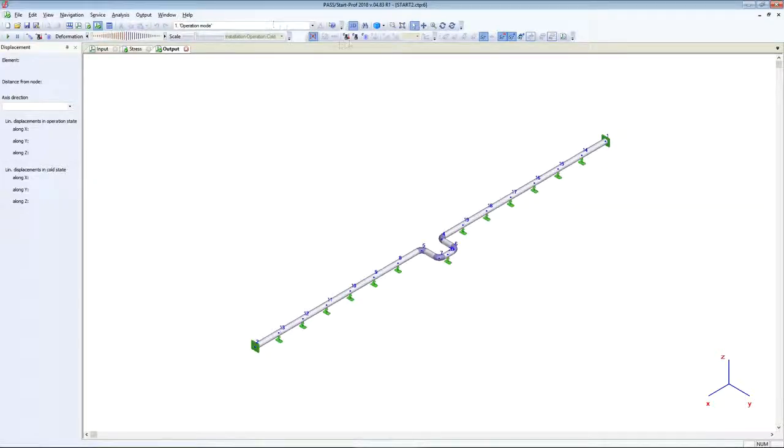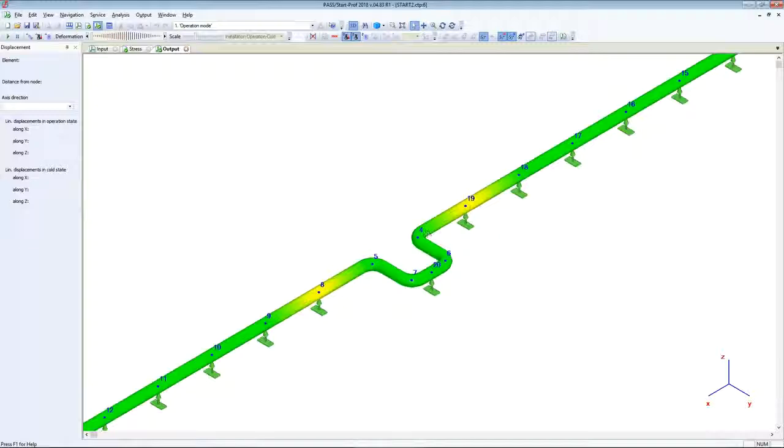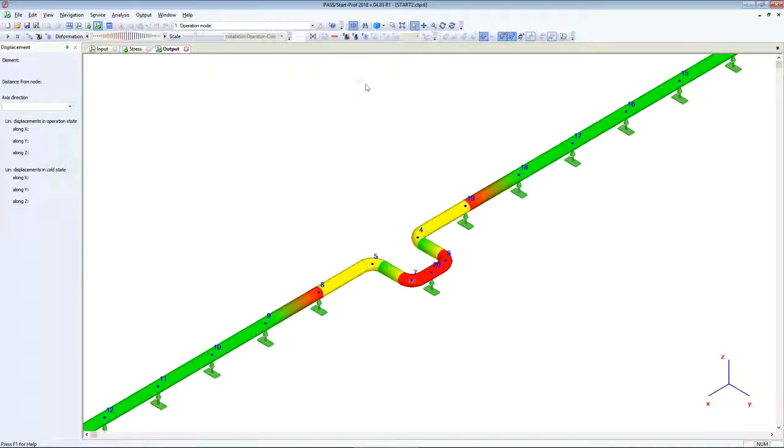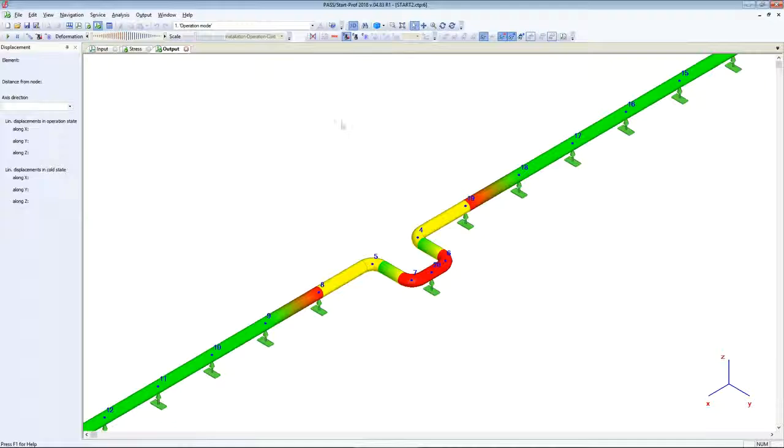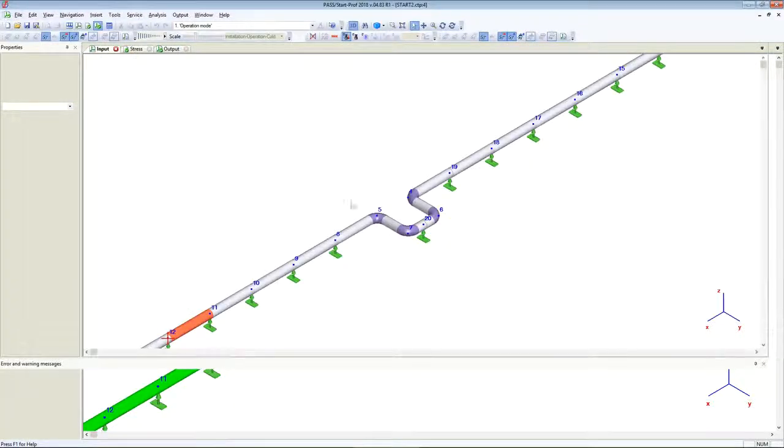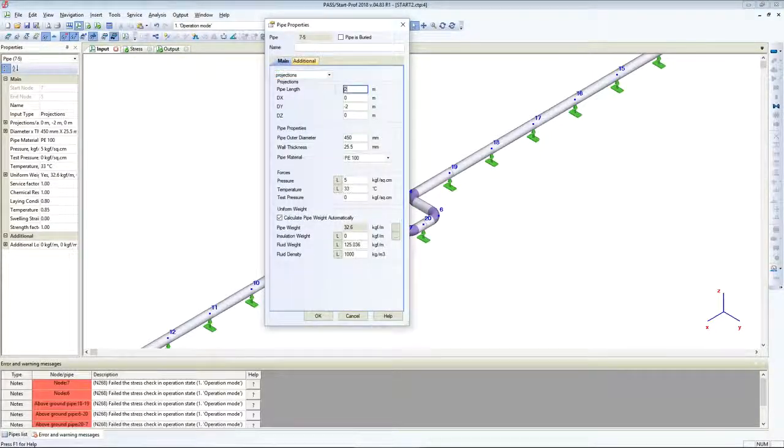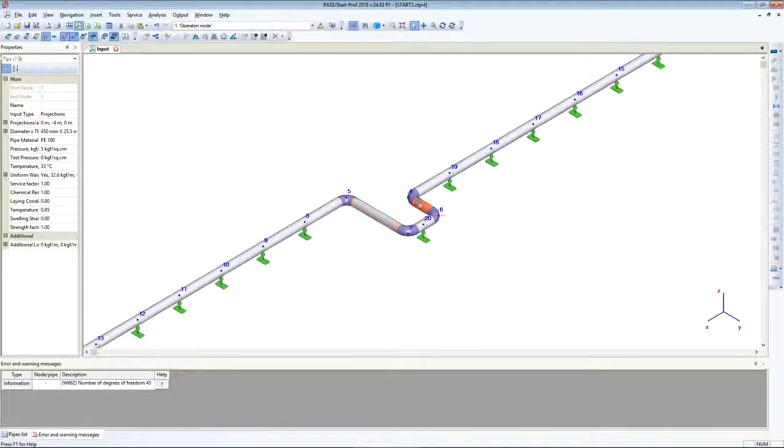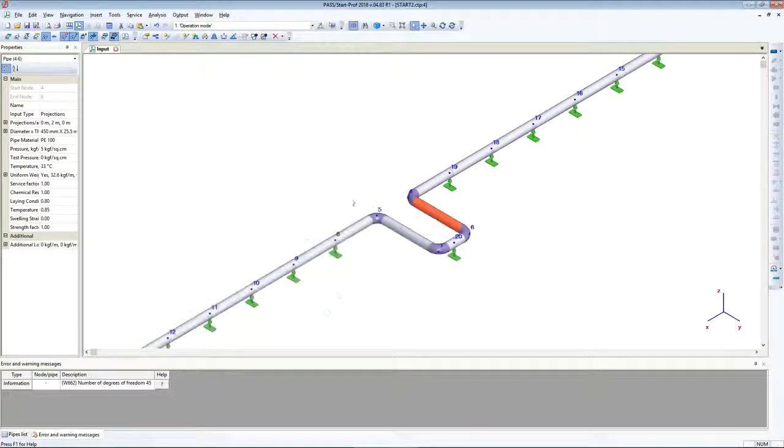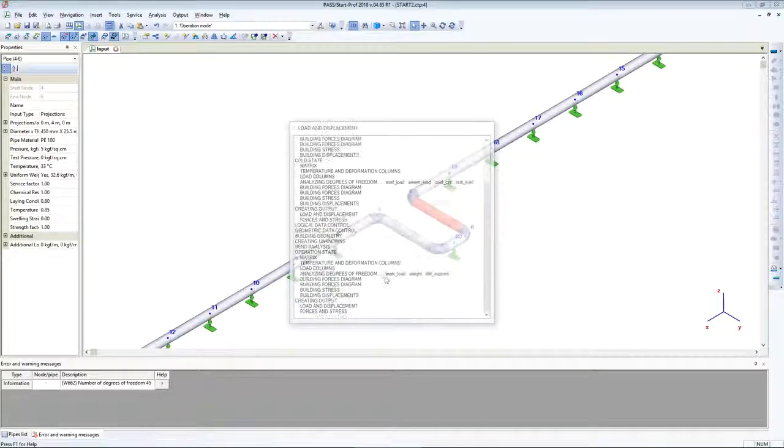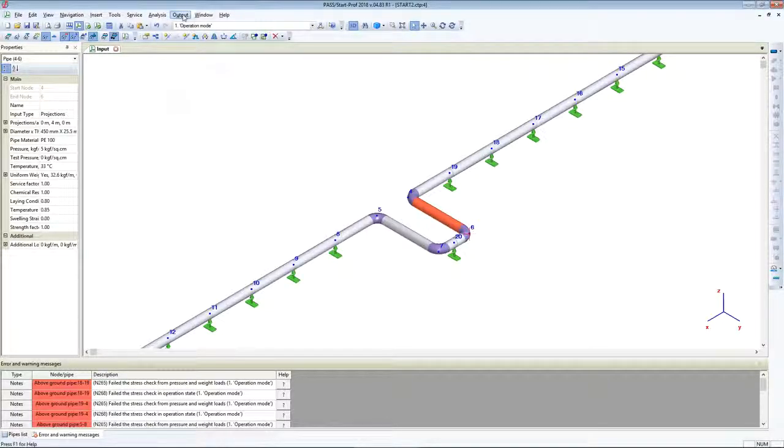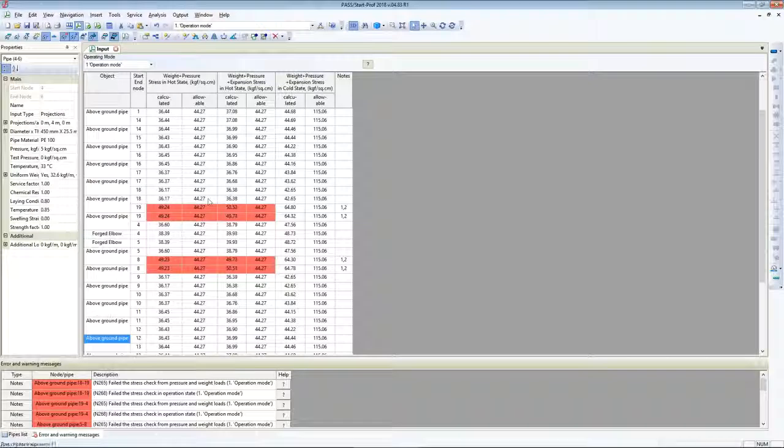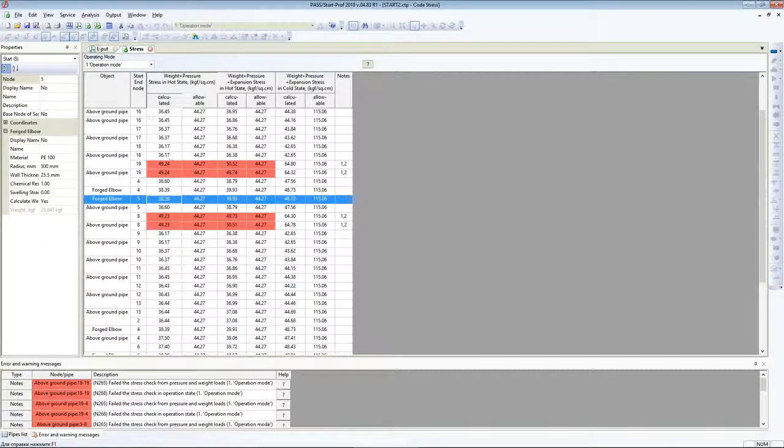But we have a problem with expansion loads, with expansion stress. Let's increase the length of the expansion loop. I will set it to 4 meters and run analysis again. Now we have a problem with weight loads again.